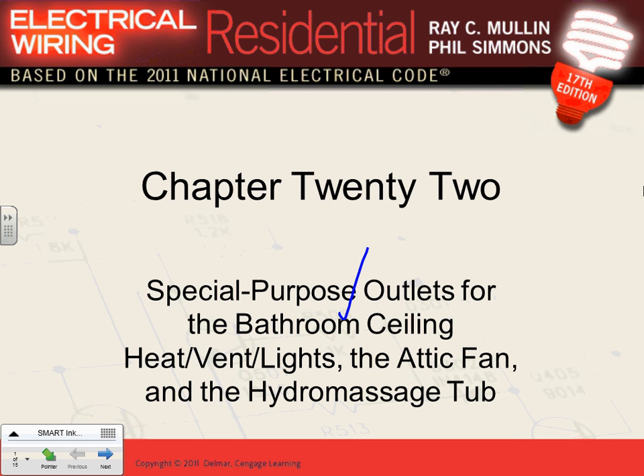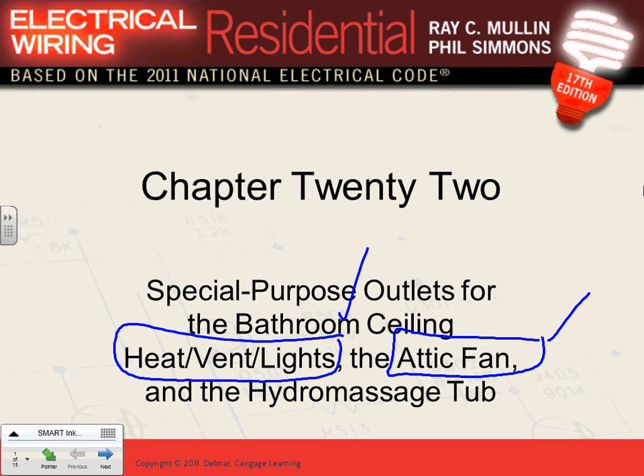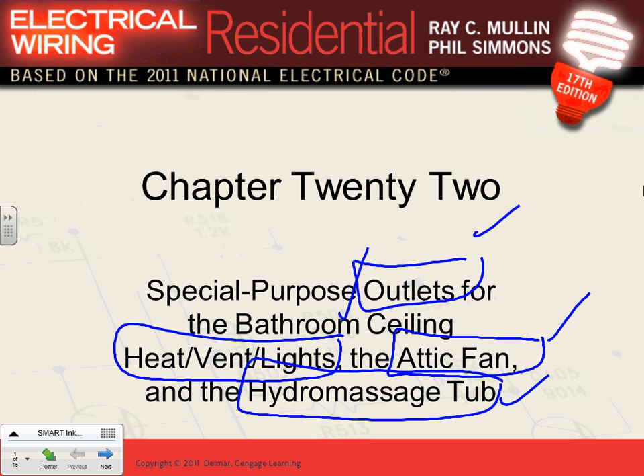Can I have a thumbs up, Chad? We understand that one? So for this big combo here, I need a dedicated circuit. I have a fan, also typically a dedicated circuit. Hydromassage bathtub, dedicated circuit. And I have an outlet, dedicated circuit. So that's basically what we're doing here. One of these dedicated circuits, 20 amp. So I have a 20 amp that feeds the outlet in the bathroom, another 20 amp that feeds the light, vent, heat combo. You're going to look at that fixture. And another one for a fan, an attic fan, typically fed from a 20 amp circuit, though you can feed it from the surrounding circuit if it's not big. And definitely the hydromassage bathtub, you need a 20 amp circuit dedicated to the hydromassage bathtub, feeding a GFCI plugged in. Can I have thumbs up?